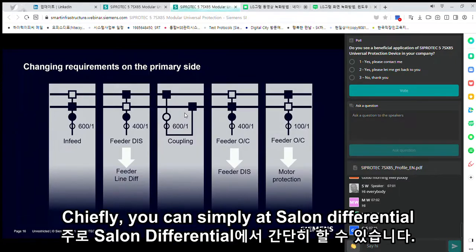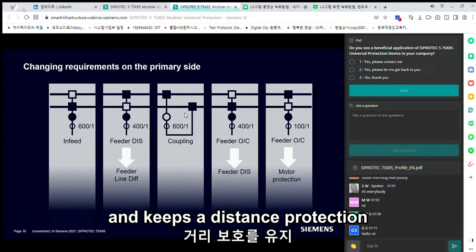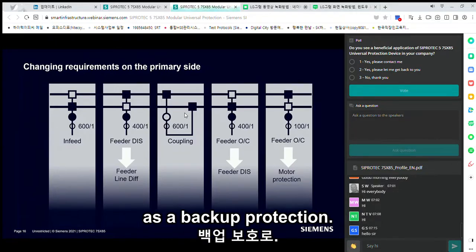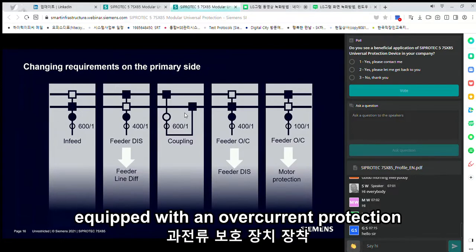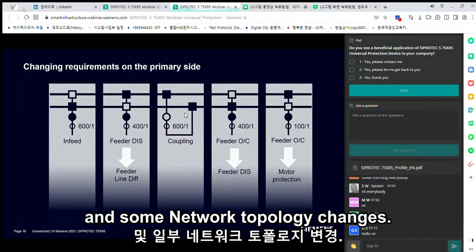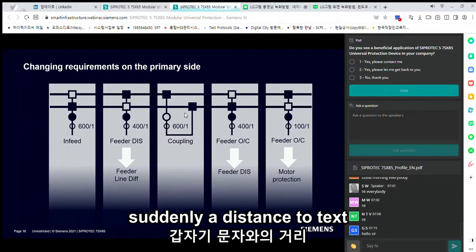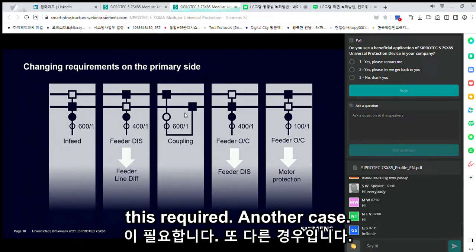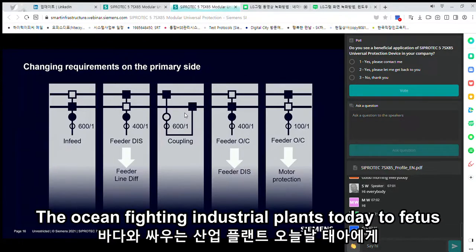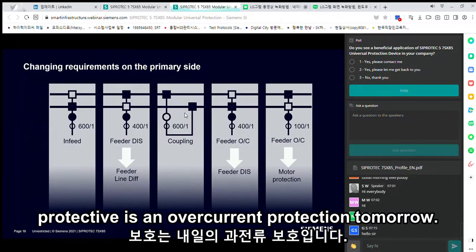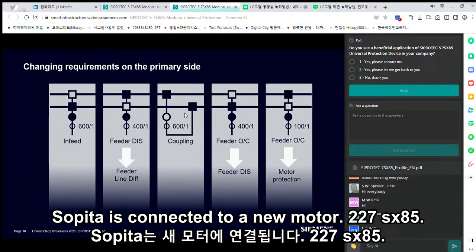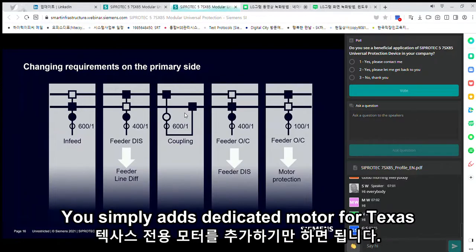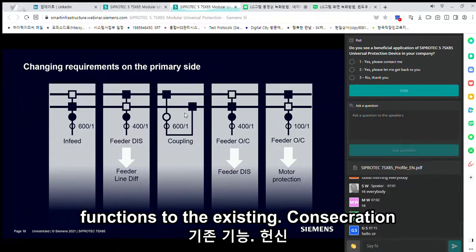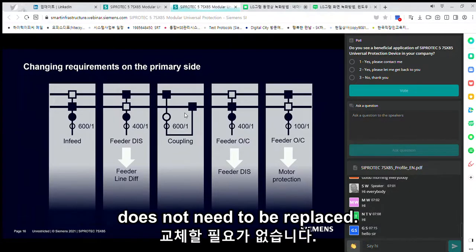Alternatively, you can simply add the line differential and keep the distance protection as a backup protection function. Or a feeder is equipped with an overcurrent protection and the network topology changes so that suddenly a distance protection is required. Another case we often find in industrial plants. Today, the feeder is protected with an overcurrent protection. Tomorrow, the feeder is connected to a new motor. With the 7SX85, you simply add the dedicated motor protection functions to the existing configuration. The device hardware itself does not need to be replaced.